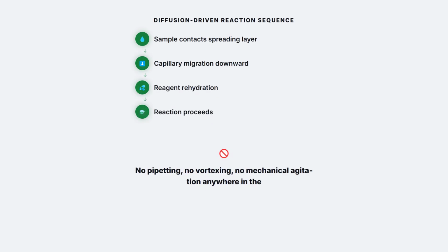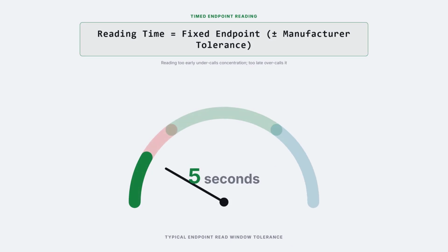The moment a sample drop contacts the spreading layer, diffusion, not active mixing, drives everything that follows. Water and dissolved analyte move downward through each layer purely by capillary action and concentration gradient, rehydrating dried reagent as they go, with no pipetting, no vortexing, no mechanical agitation anywhere in the process. Reaction kinetics in this confined, diffusion-limited environment behave differently from an open cuvette. Timing matters intensely. Most colorimetric slides are read at a fixed, tightly controlled endpoint time, because the color continues developing after the theoretical reaction endpoint. Reading too early undercalls the true concentration. Reading too late overcalls it.